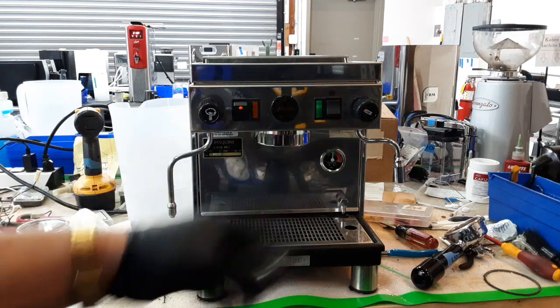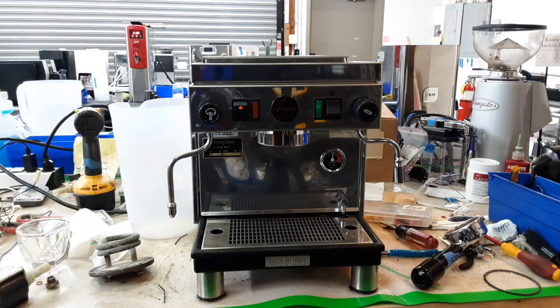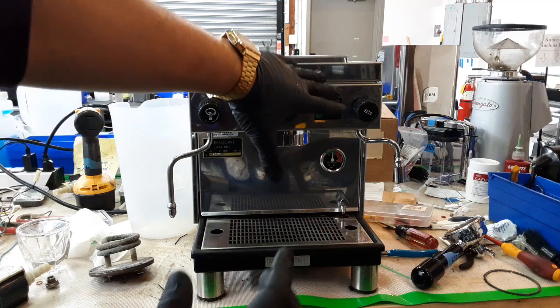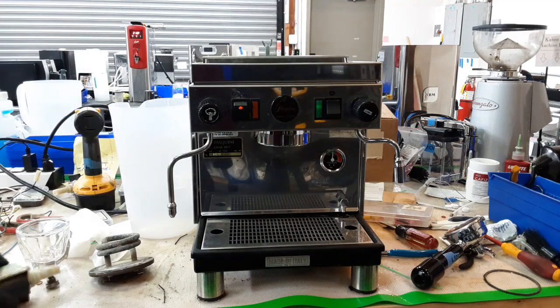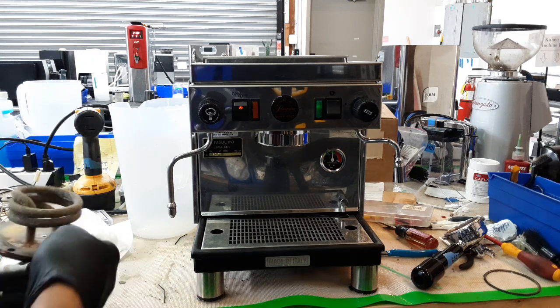We replaced the vacuum release and the safety valve as well. We also had to flip the three-way valve, as it was installed incorrectly. We had to correctly install it. We also heavily descaled the boiler.